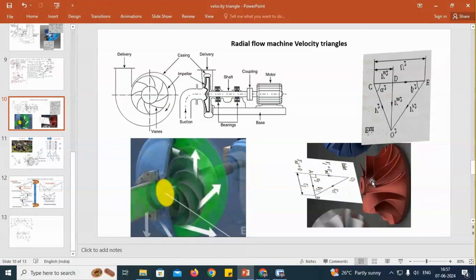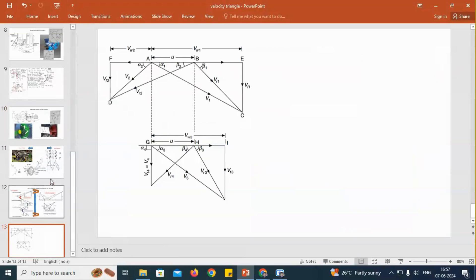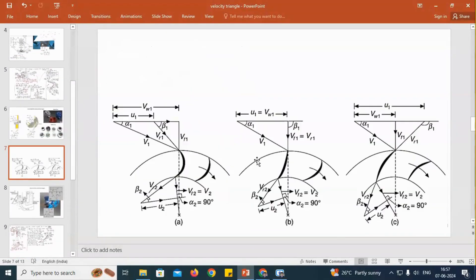For multi-stage pumps, you can add mixed flow impellers — the discharge of one pump is given to the next pump. Like this, we have a number of stages. We draw the velocity triangles either keeping the base common if tangential velocity U is the same, or if radial flow velocity Vf1 equals Vf2, we can keep the tip of the triangle same and join inlet and outlet velocity triangles together keeping Vf same. In that case, U1 and U2 may be different because it is a radial flow machine.